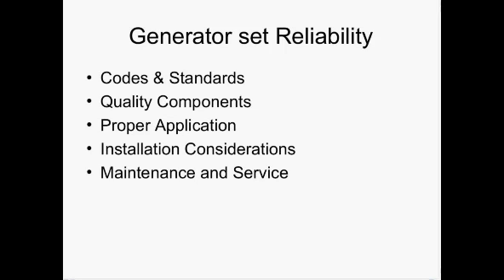The generator set must be installed properly to ensure it will cool, breathe, and expel exhaust gas safely, operating as designed without interfering with other building systems or surrounding conditions. The fuel supply must be easily serviced and installed to operate reliably. A rigid maintenance and service program is essential to ensure reliability over time.